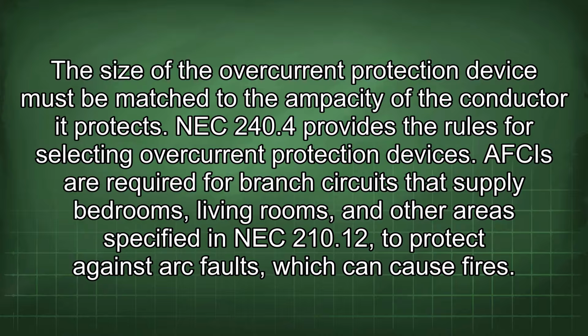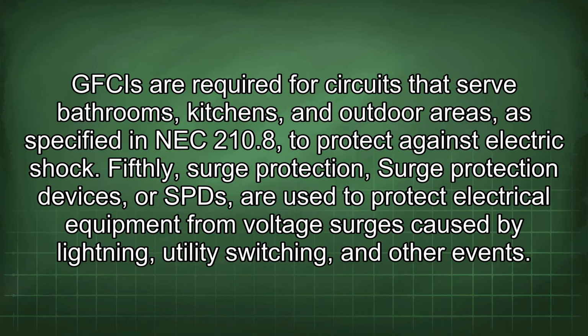AFCIs are required for branch circuits that supply bedrooms, living rooms, and other areas specified in NEC 210.12 to protect against arc faults, which can cause fires. GFCIs are required for circuits that serve bathrooms, kitchens, and outdoor areas, as specified in NEC 210.8 to protect against electric shock. Fifthly, surge protection.